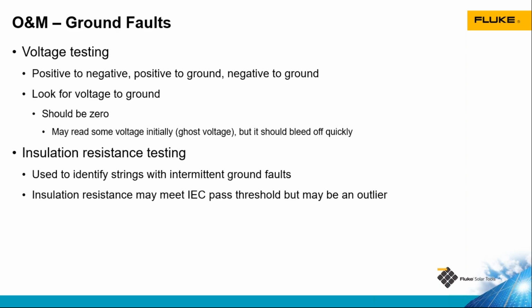On some occasions, the insulation resistance may be greater than the 1 megaohm required by the IEC standard, but less than what you're seeing from other circuits that are in the same conditions. That often tells you there's a problem there. For example, I was doing some testing on a low slope commercial roof. Every string was hitting the maximum of my meter, which was 2 gigaohms, except for one string that tested out at 156 megaohms.